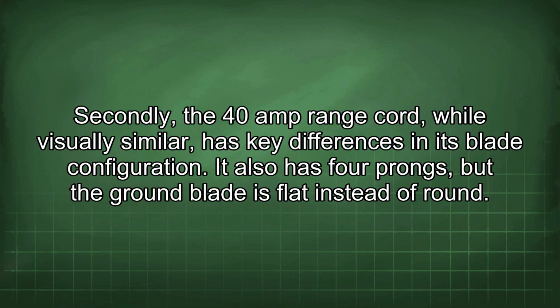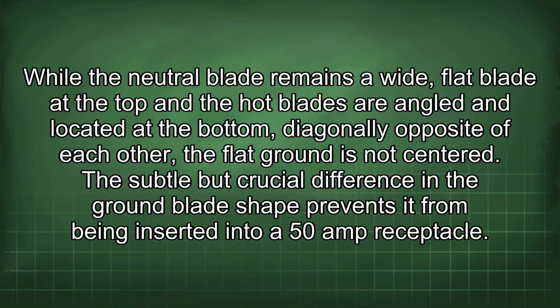Secondly, the 40 amp range cord, while visually similar, has key differences in its blade configuration. It also has 4 prongs, but the ground blade is flat instead of round. While the neutral blade remains a wide, flat blade at the top and the hot blades are angled and located at the bottom, diagonally opposite of each other, the flat ground is not centered. This subtle but crucial difference in the ground blade shape prevents it from being inserted into a 50 amp receptacle.